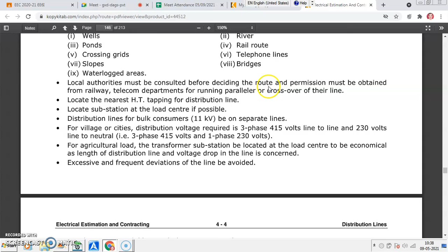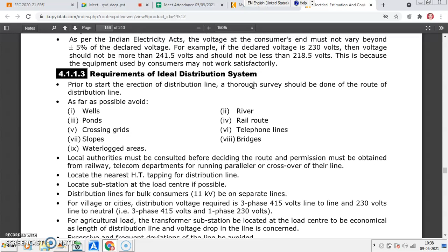So these are the important aspects as far as the ideal distribution network is concerned. Prior to starting any erection of the distribution line, you should check that there is no obstacle like a river, well, pond, or telephone line. All these, you have taken suitable permissions, you have the nearest HT location decided for the tapping, and the distribution lines running for the bulk consumers are separate lines. They are not in conjunction with other substations. You have a well planned 3-phase 4-wire or 3-phase 3-wire system for agricultural and local or rural or village consumers. You have avoided excessive and frequent deviations or disturbances to the lines.